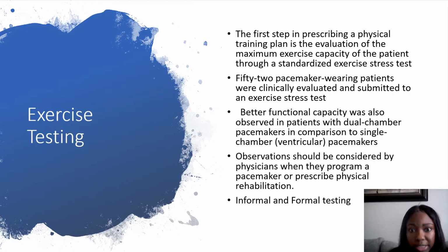And then formal testing is recommended for active individuals who likely want to reach their max sensor rate. The protocol selected requires careful consideration, so it's called the chronotropic assessment protocol that's recommended for individuals with a pacemaker. The advantage of this protocol is the stage gradually increases to mimic the range of activeness at daily living. So this protocol allows a more complete assessment of how the pacemaker responds at a lower metabolic rate, where the individual usually spends more of their time.